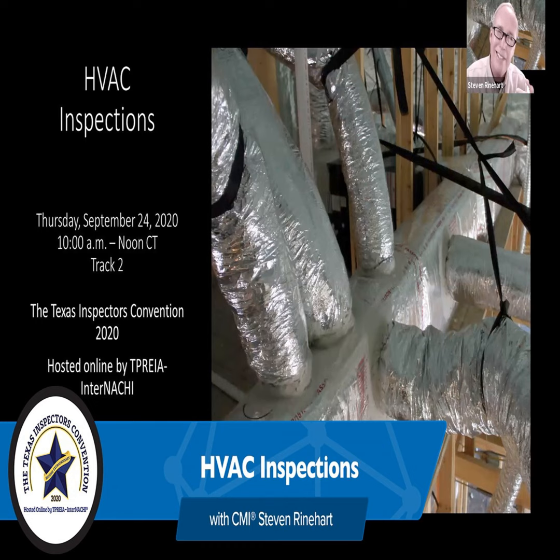There will be two, I didn't get a picture of them, there'll be two 3-inch PVC ducts, one intake and one exhaust coming out of the left end of this air handler, and it'll go up through the roof. In a lot of places, it'll combine just before it goes in with a specialty exhaust flue, kind of a triple wall flue that'll go up through the roof deck.